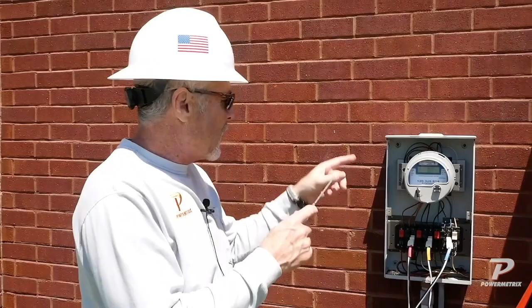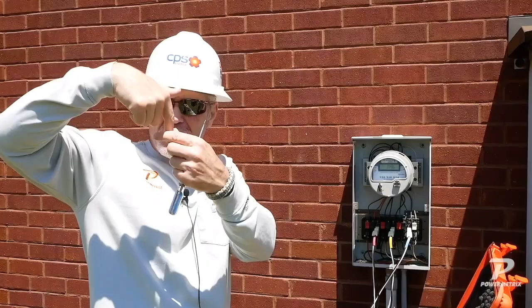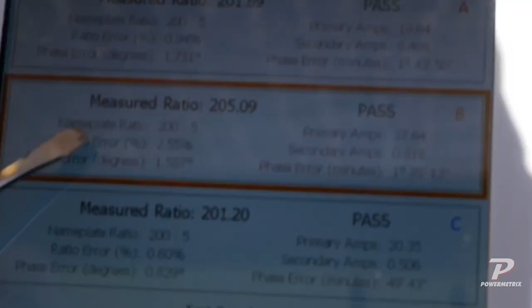So then last but not least, you come in here, pull the meter, and get your screwdriver. On B phase, loosen those screws and then tighten them back in. When we did that, obviously you're working those threads and those connections right there. Come over here and take a look. We ran the test again, and now we got a pass on it.